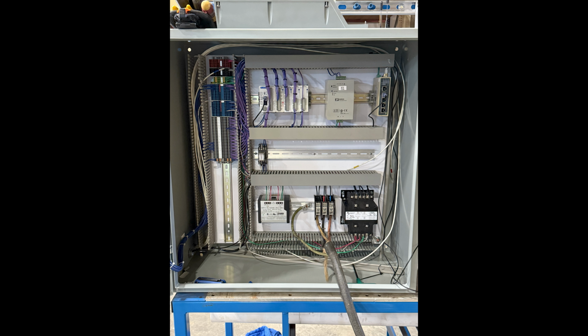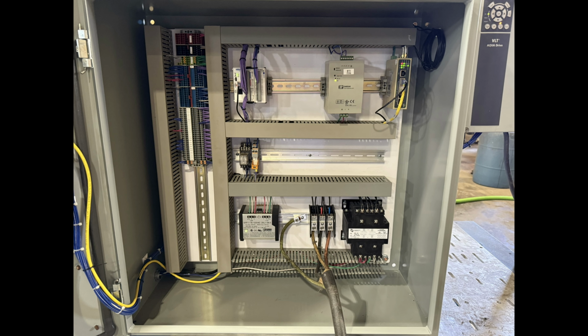So here is what the panel had looked like before we had to remove the bad analog input-output cards and also change out the PLC. And here is what the panel looked like after. As you can tell, we have a lot more room up top with those 3 modules getting taken out. In the bottom right, you can see the transformer, the big black brick you see there. It's being fed by those 3 terminals to the left of it from our 240 coming in, going to the transformer, and then carrying on to our 120 terminal blocks, going to the 24-volt power supply. You can see our surge protector, our cellular modem in the top right, and obviously the PLC in the top left.